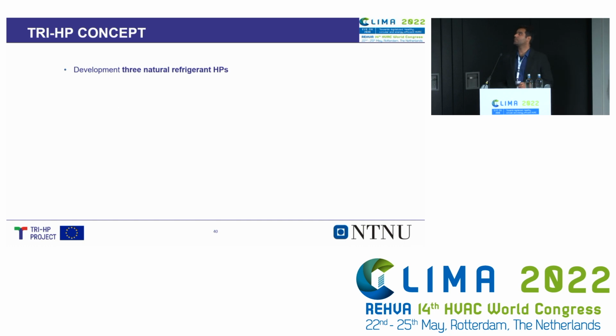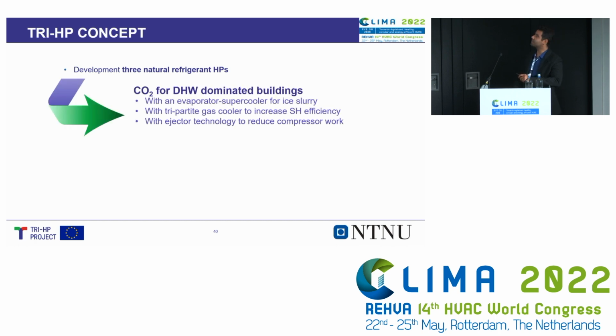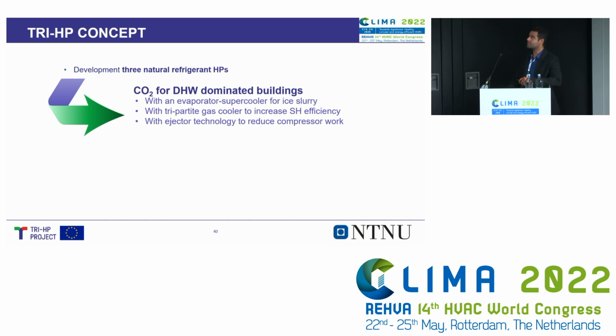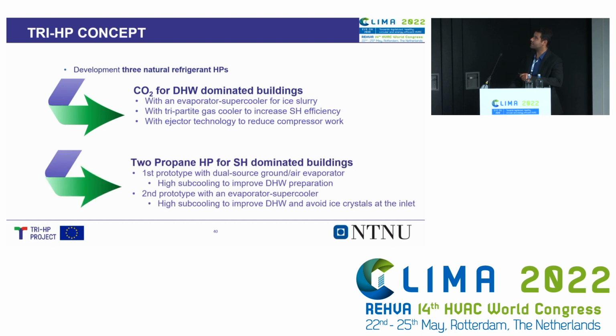All right, so through the TRI-HP project, as my colleagues mentioned, we developed three natural-based refrigerant heat pump systems. The first prototype is based on CO2 refrigerant for buildings. When domestic hot water is dominant, we utilize the auxiliary system concept, the tripartite gas cooler, to improve the efficiency of the unit, and we also utilize ejector technology to reduce the compressor work and recover some of the losses that we face.